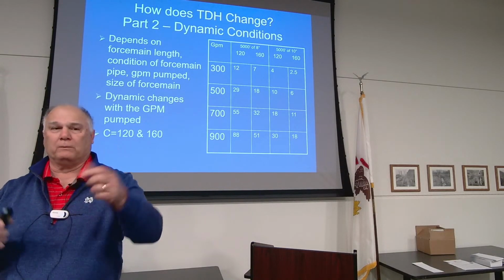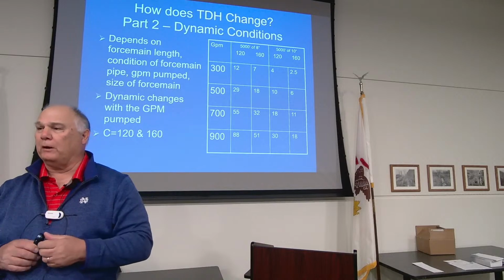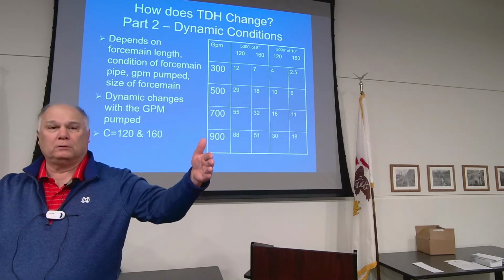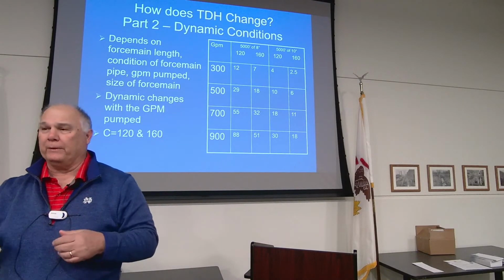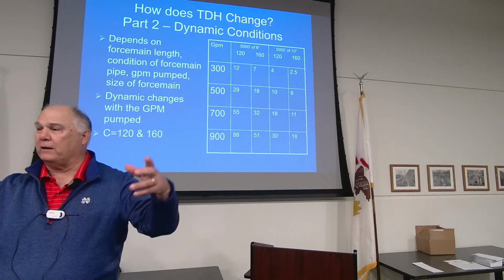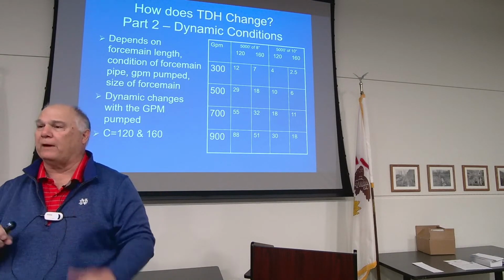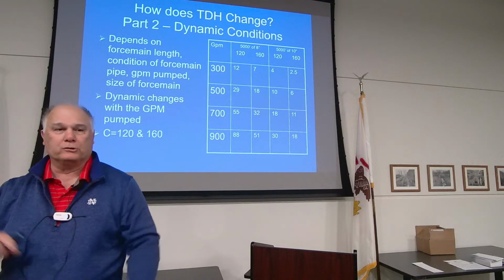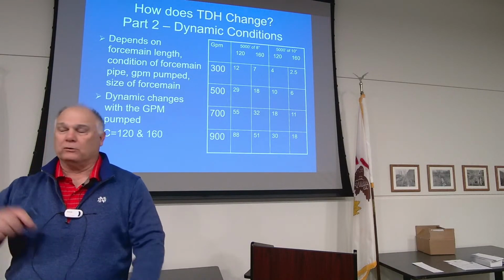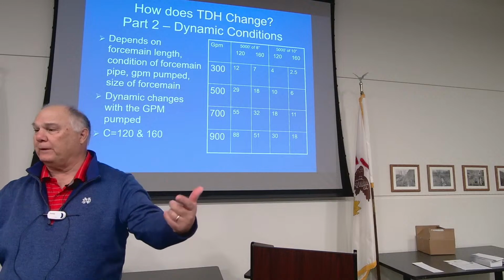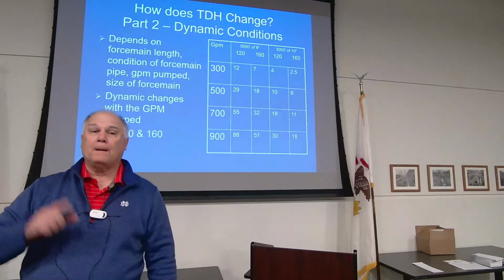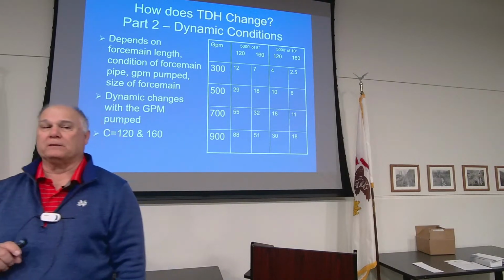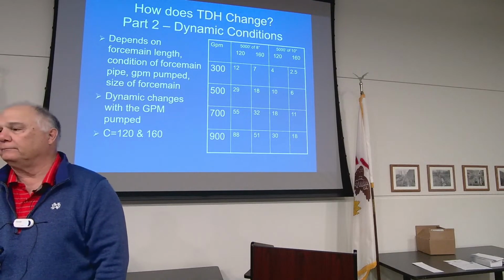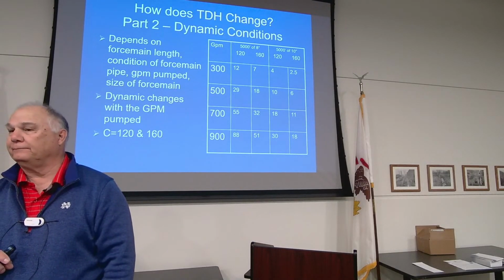A pump down test is when we time it. We turn the pump on, force main's full. We time how far it goes down in a certain diameter and how much volume we're pumping in a certain amount of time. So time versus volume gives us GPM. But what's one important thing about a pump down test you've got to be careful of? Anybody?